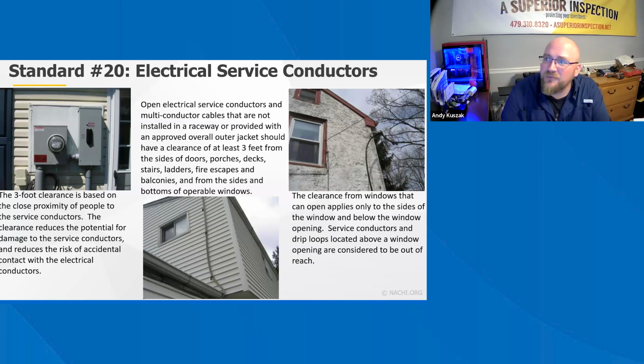No clearance is required from windows that do not open. Electrical service conductors should have a vertical clearance of at least 8 feet above the roof surface. There are exceptions. The 8-foot vertical clearance above the roof surface should also be maintained for at least 3 feet horizontally from the edge of the roof, except when the service drop is attached to the side of the building.